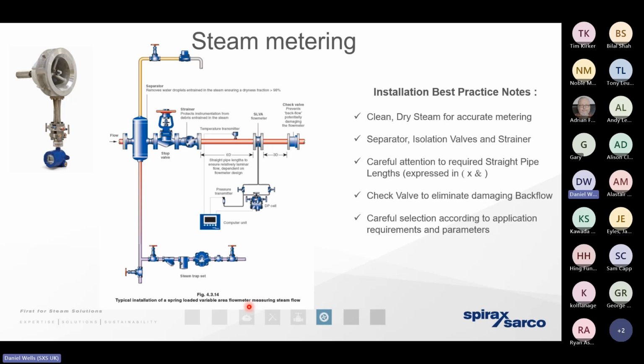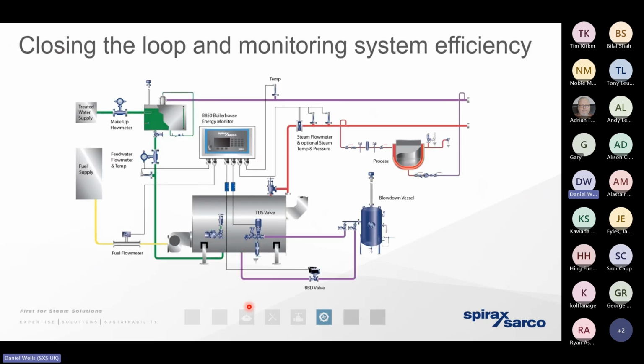So, as we've mentioned, steam metering. It's important to meter the steam at the point of generation. It's important to meter the steam at the point of use, so we can put a value on each individual steam using process. So we can understand how much steam is going missing when it's being moved from the boiler to each individual process around site. But we can also use it for diagnostic purposes. For example, if our heat exchanger is calling for more and more steam over a period of weeks, it could be that the steam's wetter and wetter, so there's less energy present within it. Or it could mean that there's a lot of foam that's creating a barrier to heat exchange and slowing the process down. So it's not just for energy observations, it's also for diagnostic purposes as well.